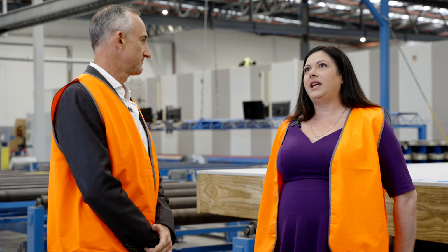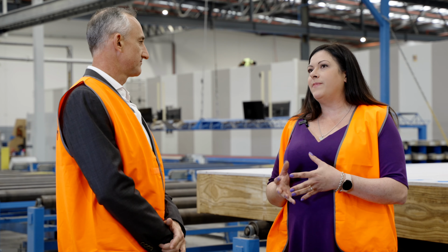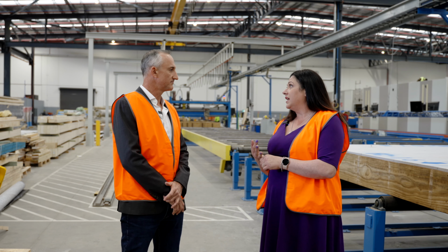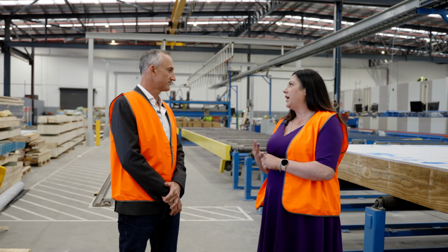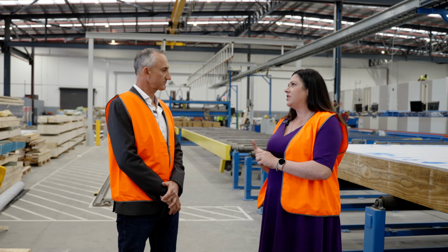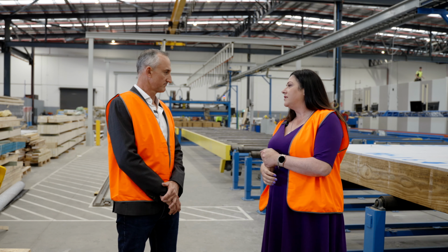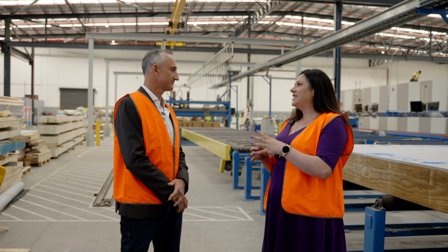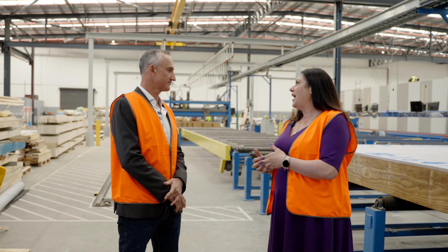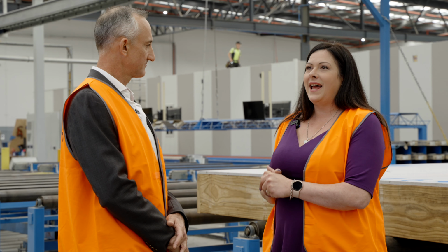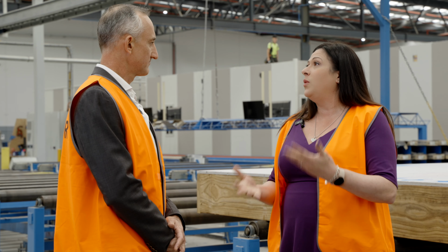Passivhaus is essentially a building methodology which is made up of 5 basic principles, being increased thermal insulation, double glazed thermally broken windows, heat recovery ventilation, thermal bridge-free design, and airtightness. So it all ties together using the Passivhaus modelling software. That ties all the elements together and gives you your outputs for your energy usage, your performance, and where there might be some lagging in the performance of the dwellings and how we can improve on that.